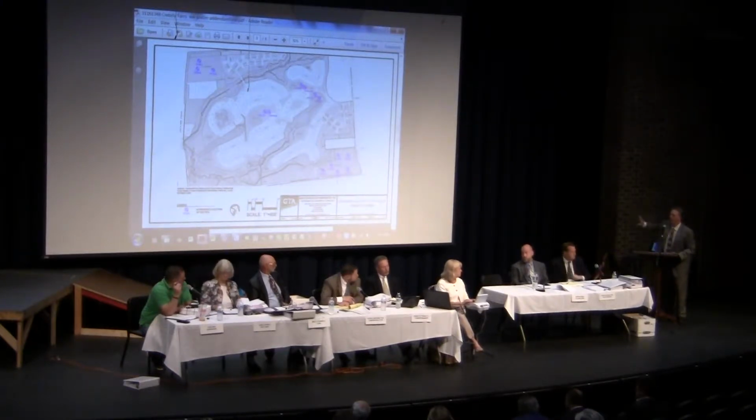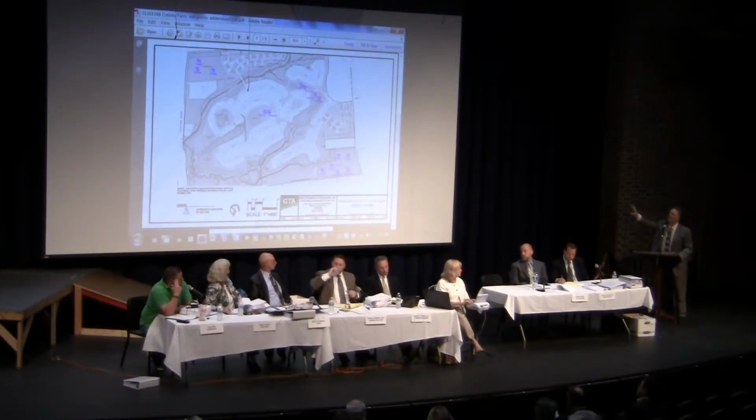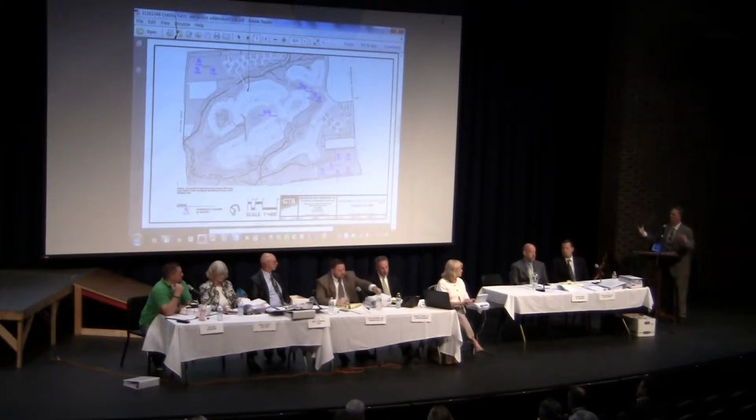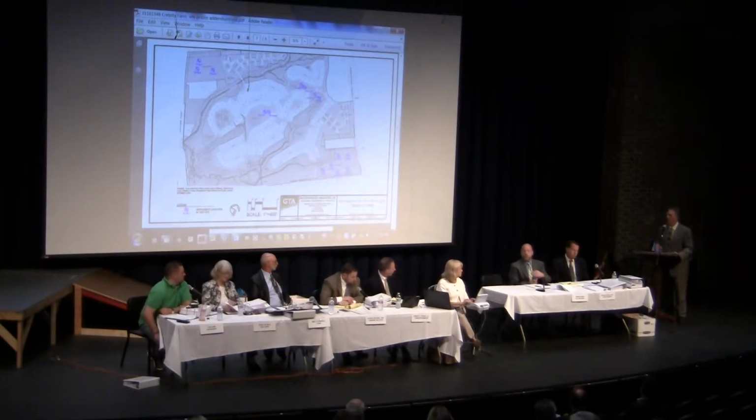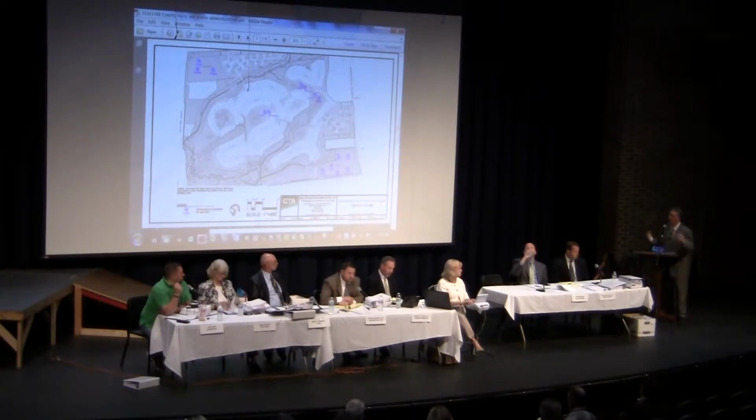In order for me to determine, did the soil scientist who testified before me identify sufficient areas that I felt comfortable testifying there was enough disposal capacity? That's how I did that; if it was 80,000, I wouldn't feel as comfortable. He has approximately 10% over, so if there are areas that get removed, which happens. The rule of thumb that I use is I always design 110% when I start the approval process, because through the mounding analysis, through soils, through something, I lose 10%. I always anticipate losing something.